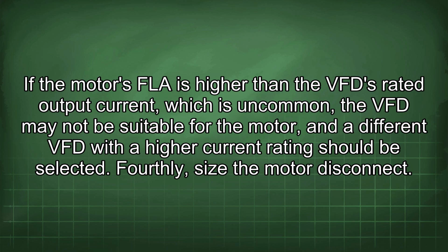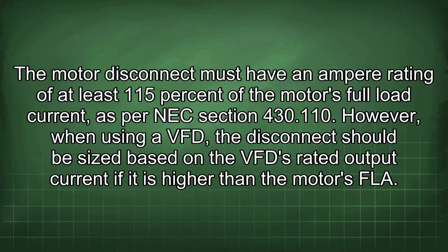Fourthly, size the motor disconnect. The motor disconnect must have an ampere rating of at least 115% of the motor's full load current, as per NEC section 430.110. However, when using a VFD, the disconnect should be sized based on the VFD rated output current if it is higher than the motor's FLA.